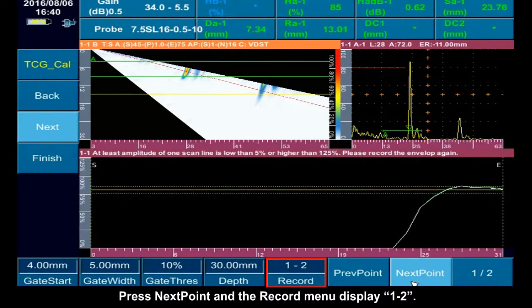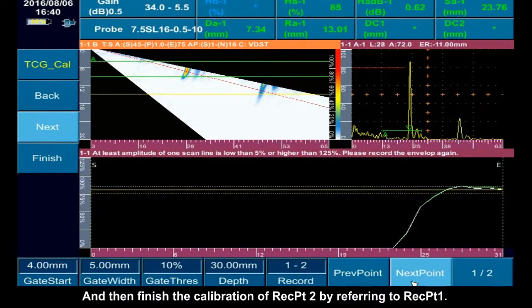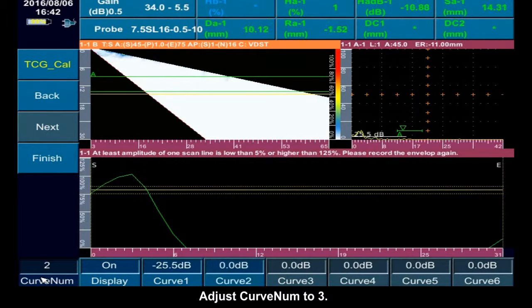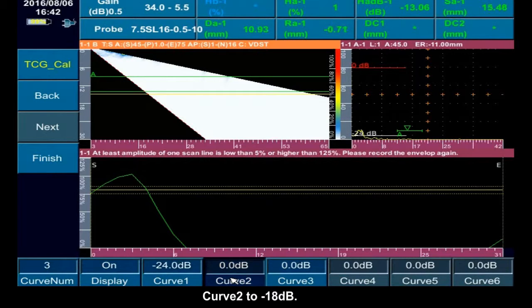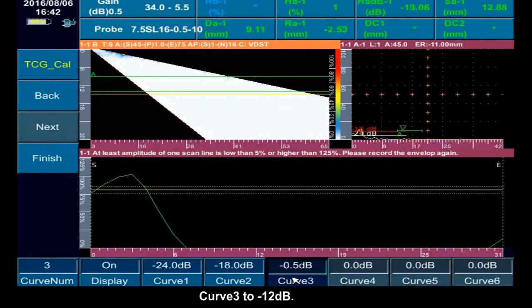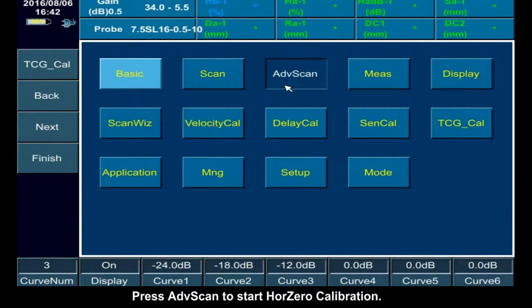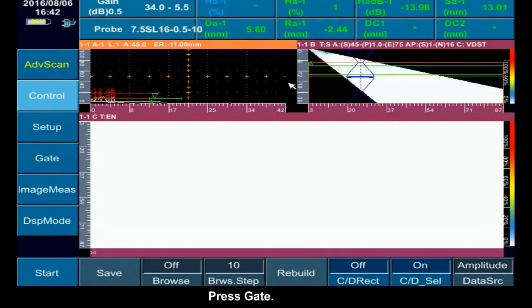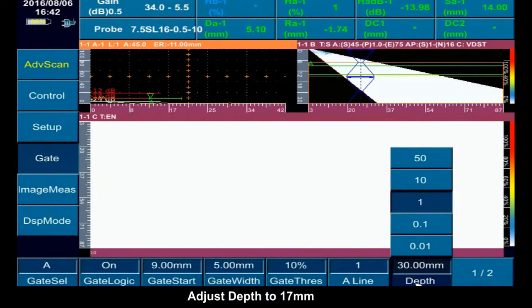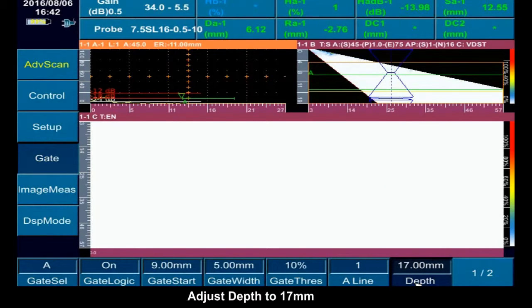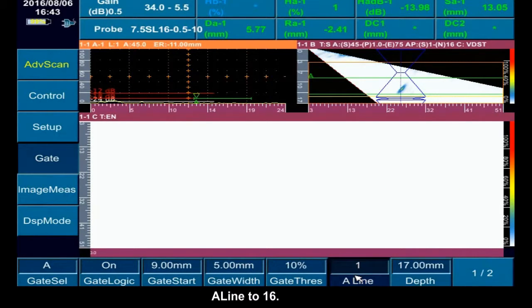Press Next point and the record menu displays 1-2, and then finish the calibration of reference point 2 by referring to reference point 1. Adjust curve number to 3, curve 1 to -24 dB, curve 2 to -18 dB, curve 3 to -12 dB. Press Finish. Press Advanced scan to start horizontal zero calibration. Press Gate. Adjust Depth to 17 mm. A-line to 16.